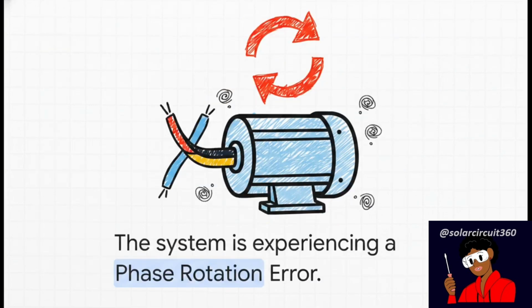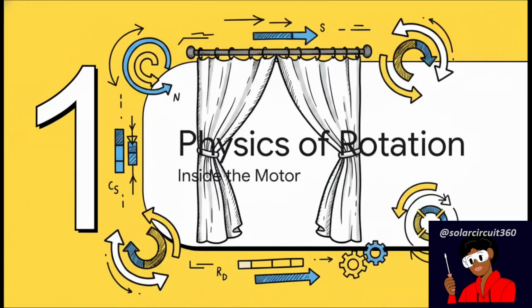Well, the answer is a phase rotation error. That's the invisible culprit causing all of this mechanical chaos. You see, an electric motor doesn't actually inherently know which way it's supposed to spin. It just blindly follows the electrical instructions it's given. And if those instructions get mixed up, even just slightly, that motor will happily operate at full power in the exact opposite direction it was engineered for. No questions asked.